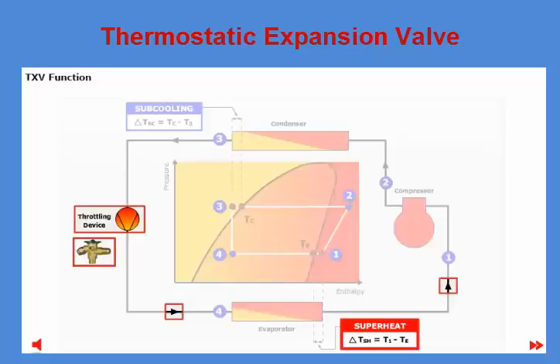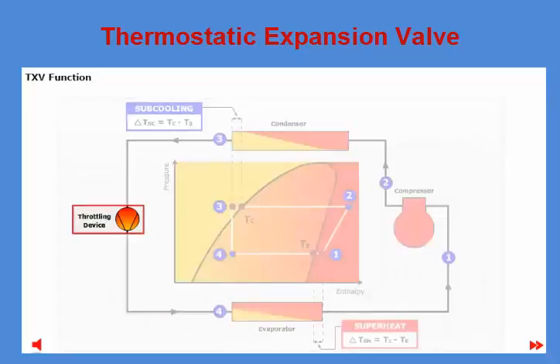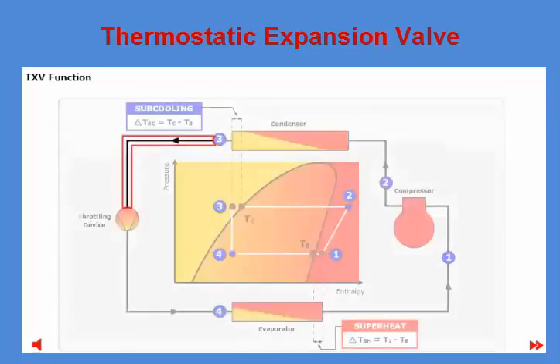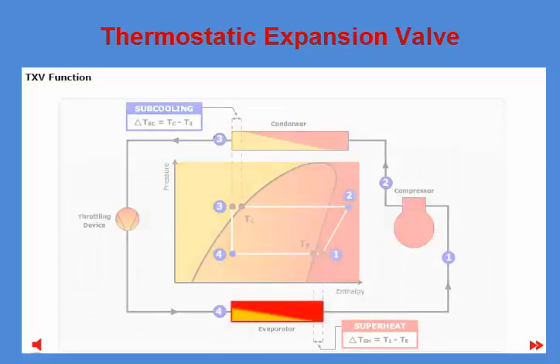This is where the TXV has a huge advantage. Because the TXV is a modulating valve, it will regulate the injection of liquid refrigerant in the evaporator in proportion to the actual operating conditions. This means it prevents liquid passing to the compressor independent of operating conditions. For the expansion valve to operate correctly, it's important to always have 100% liquid in its inlet connection. To guarantee this, a certain minimum subcooling must be maintained in the liquid line at point 3. If this is not possible, flash gas may develop in the inlet of the throttling device, leading to starvation of the evaporator.